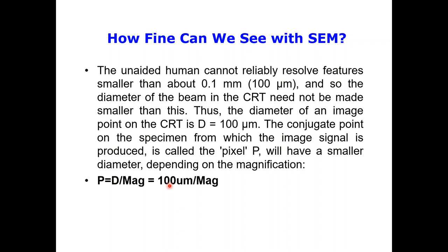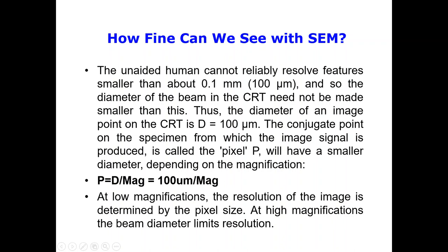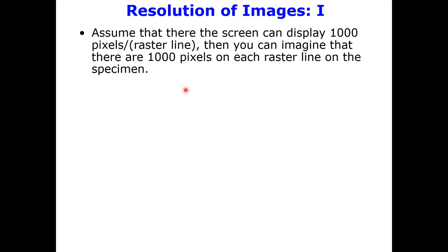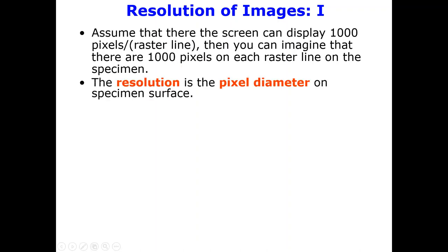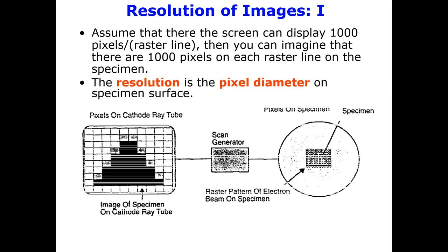At low magnifications, the resolution of the image is determined by the pixel size. At high magnifications, the beam diameter limits the resolution. Assuming the screen can display 1000 pixels per raster line, you can imagine 1000 pixels on each raster line on the specimen. The resolution is the pixel diameter on the specimen surface, as shown in the diagram with the raster scan pattern of the electron beam on the specimen.